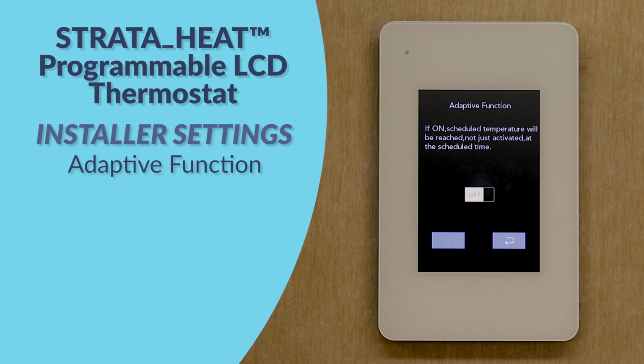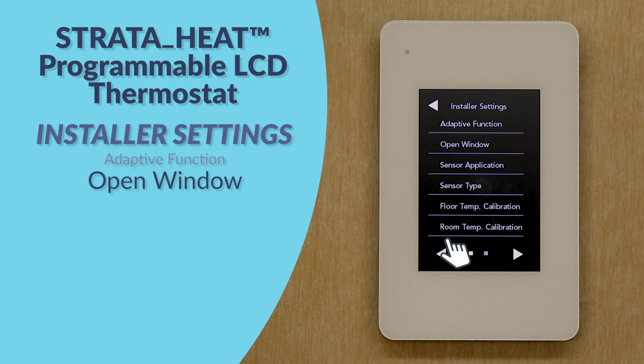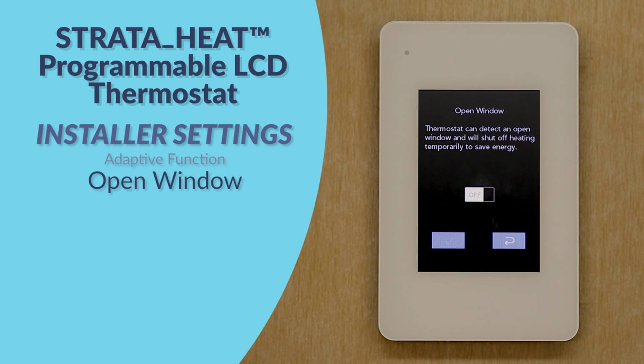When adaptive function is set to on, the thermostat will reach a scheduled temperature by a scheduled time. Setting the adaptive function to off will activate the temperature at a scheduled time. Note that whenever a checkmark button appears on screen, you will use this button to save changes and proceed. The next option in this section is Open Window. Having this set to on will allow your thermostat to detect a sudden temperature change caused by an open window or door. This will shut the floor heating off temporarily to save energy.